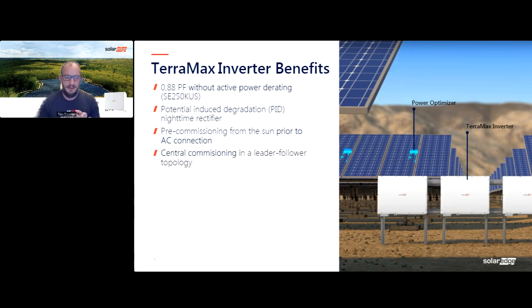Our inverters have a leader-follower topology. If you have lots of inverters, especially if you use what we call our virtual central, which Amir will touch on later, where you have inverters on a rack design, all next to each other, co-located, and connected to one transformer, you would set one up as the leader and the rest as followers. You only have to commission the leader, and then the leader will search for the followers behind it, so you're only commissioning one device. Again, it saves a significant amount of time and a lot of confusion when you're doing this on site.